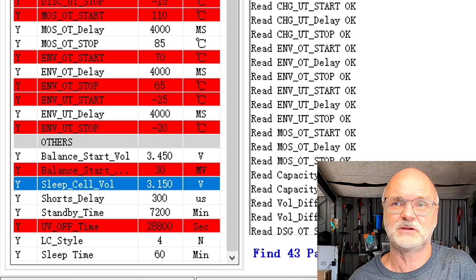Okay, so far the protection parameters are not too bad, except for the temperature parameters. They are all off. They are far too high or far too low, and they should be changed. The current parameters seem to be fine, if it is a 250 amp BMS. Again, we don't have the information. There's nothing on the website, nothing in the manual, which are linked down below. It only says a continuous discharge current of 220 amps, so I assume it's a 250 amp BMS, and then the parameters are fine.